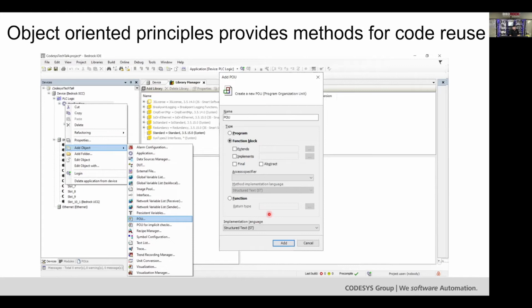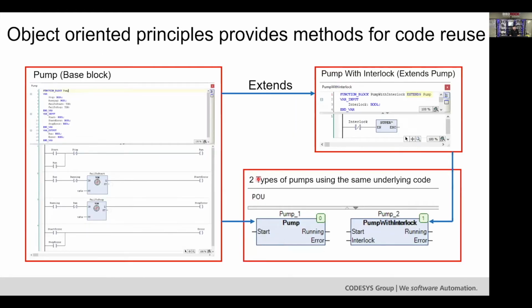So what that looks like to extend a really simple program: I made a pump. What you end up doing in this case is create what's usually referred to as a base block. You build your base pump that's going to have all the common components that will be the same across the board in any variation. With a pump in this particular case, it's going to have a start and stop, fail to start, fail to stop type logic, and a little bit of error logic. That's going to be the same across all pumps.